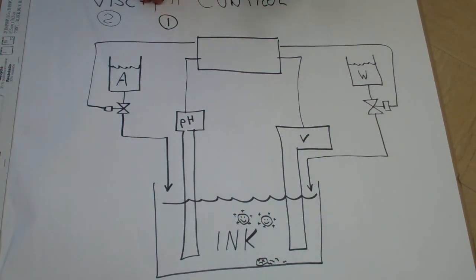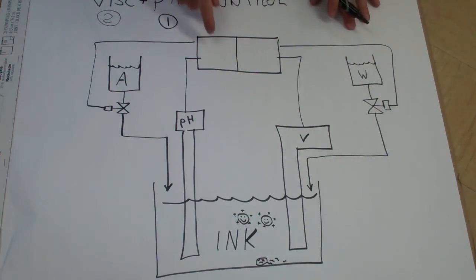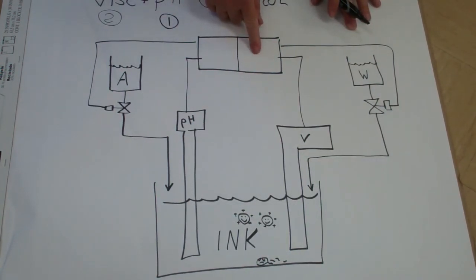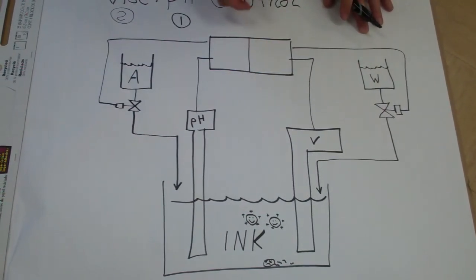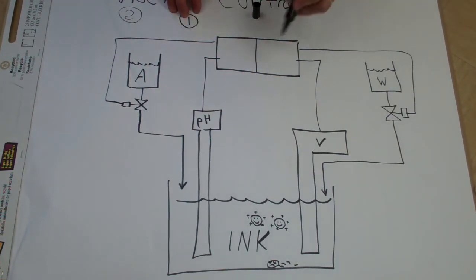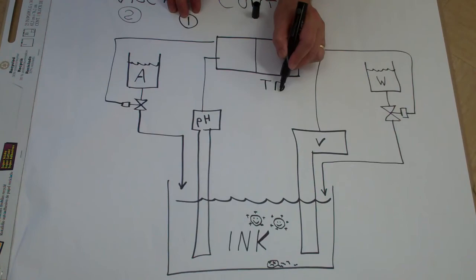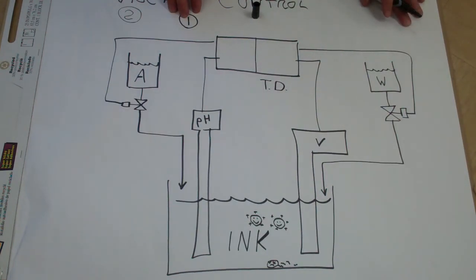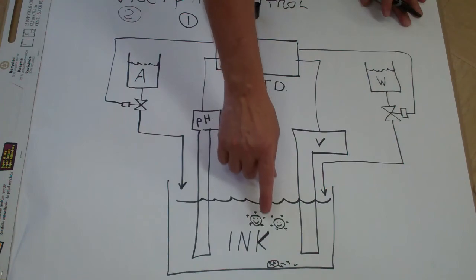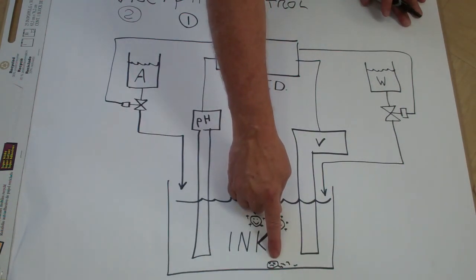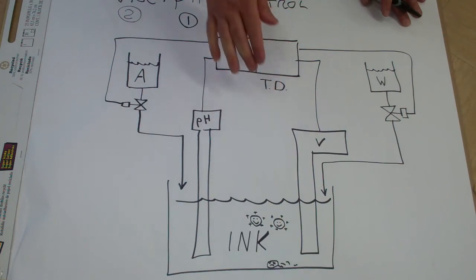The controller is actually two controllers. One half controls pH, one half controls viscosity. In the viscosity side, we put in a time delay. That's because pH is the more important parameter. So we tell the viscosity side, hey, if your viscosity is a little bit high, let's check the pH and let the pH get in balance first. Because like I said, you can reach a condition where your pH is off, your viscosity is high, you add a lot of water, and the pigment can settle to the bottom of the tank. Not a very good situation, doesn't help you to process.